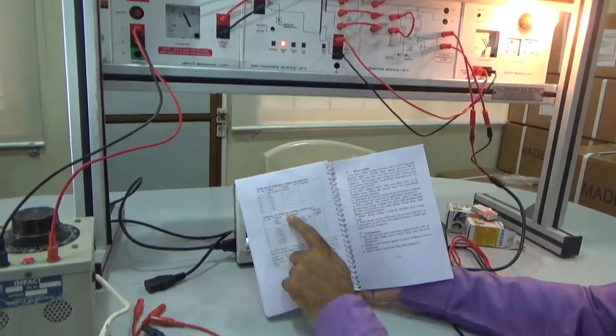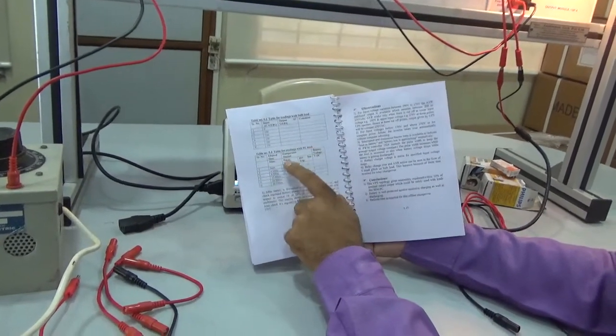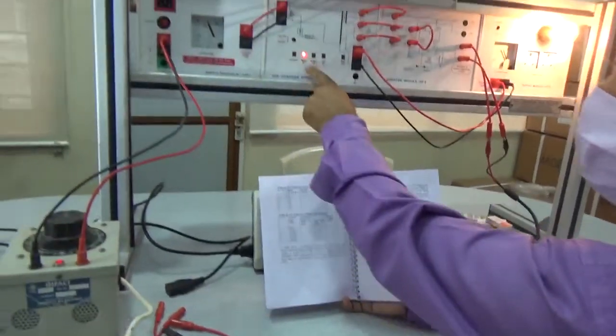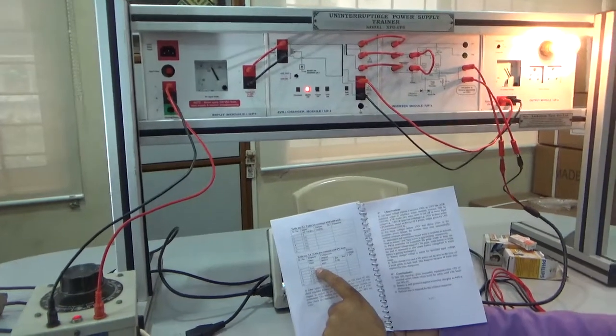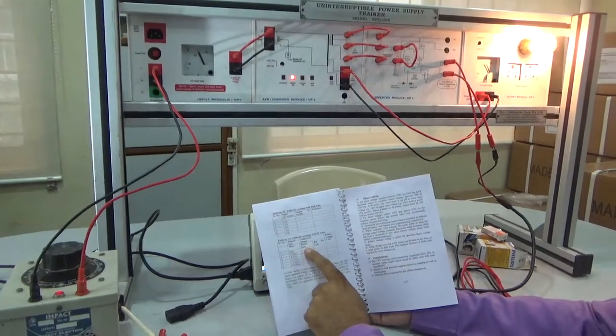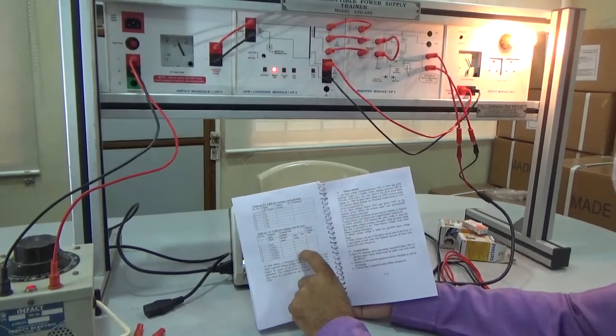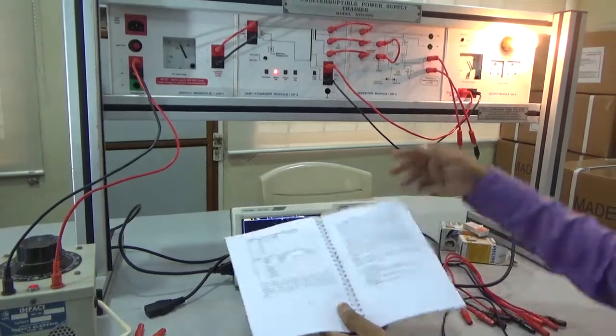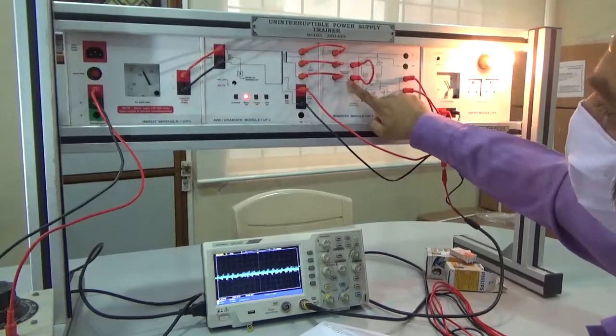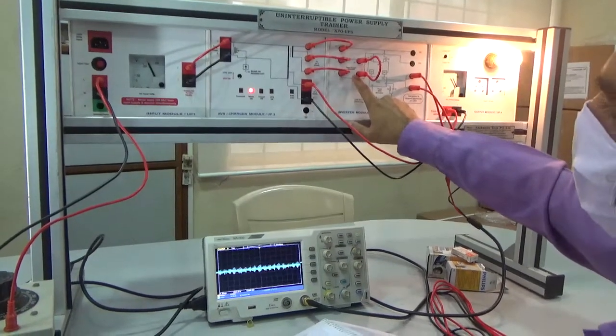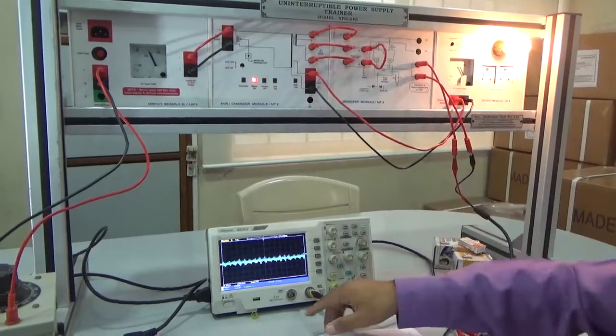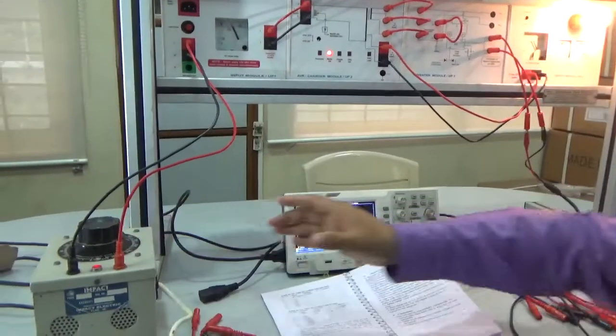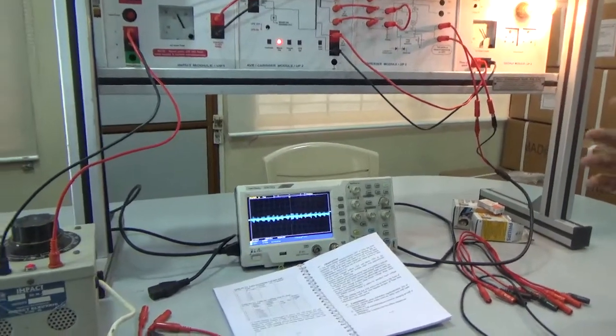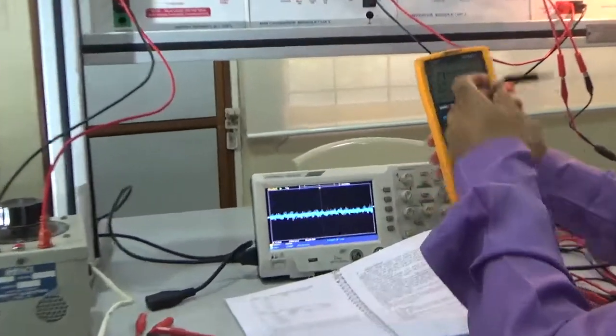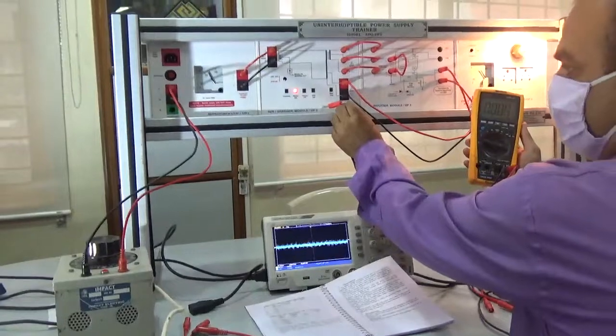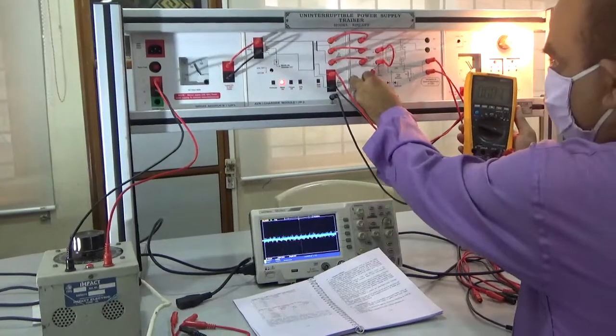Now here is another table for readings with PC load. Here we have to make mains off and UPS on, and we have to measure the timing. At that condition, note the battery low buzzer, battery low trip, and battery voltage. So we have to connect one multimeter between tag number 12 and tag number 14, that is battery positive and battery ground. Here is one digital voltmeter, a DC voltmeter. We have to connect it between ground tag number 14 and tag number 12.